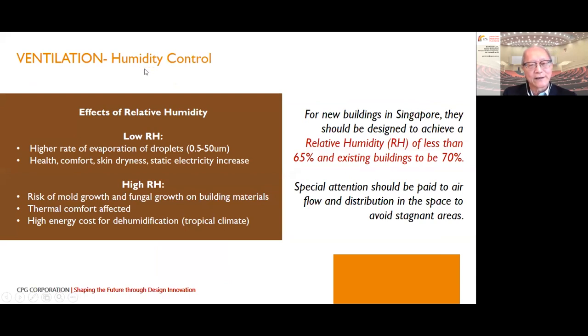How about humidity? For low humidity, we are not very concerned in the local climate. We are more concerned about high relative humidity because it encourages mold and fungus growth. For Singapore, indoor air quality practice requires relative humidity for new buildings to be less than 65%, and for existing buildings, 70%. This is the norm we design to. We also know from experience that stagnant areas could accumulate more moisture, so we pay attention to the flow and distribution of air in the space.